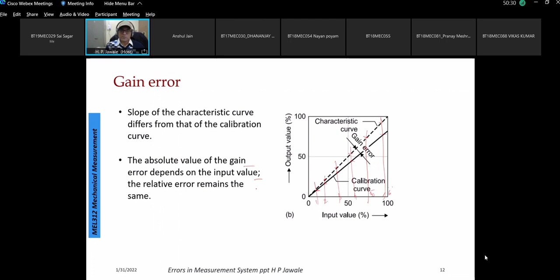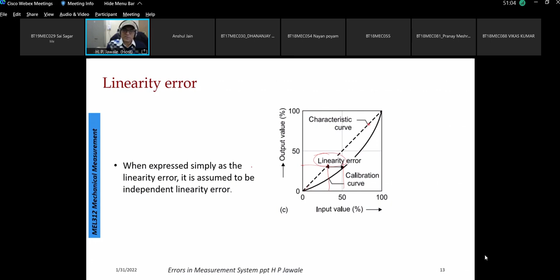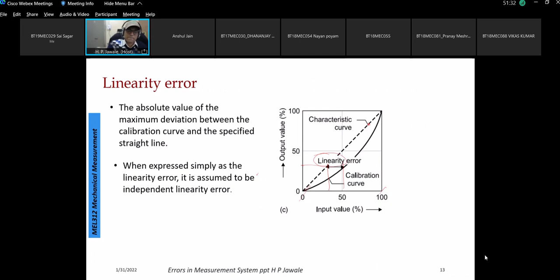Right. Then linearity error. In the characteristic curve given by the manufacturer of the equipment or the measurement system, it is expected to have a very linear relationship between input and output. But in actual practice, it is going to differ. So for a given input, at any point, we can find out the error in linearity, how much it has deviated from the linear curve. It is the absolute value of the maximum deviation between the calibration curve and the specified straight line or the characteristic curve given by the manufacturer. That is the linearity error. We express it as the maximum non-linearity of the equipment in terms of the given range of measurement and so on. So this is a general way of finding it.